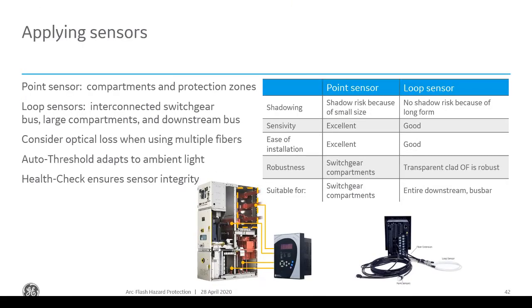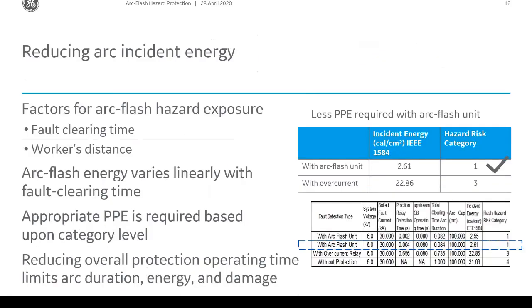So applying the sensors, the loop sensor is mostly for the entire switchgear lineup, whereas point sensors are for specific switchgear compartments. Point sensor is always going to give you excellent sensitivity. Loop sensor not so much, because we're talking about fiber degradation, fiber signal degradation, and such.